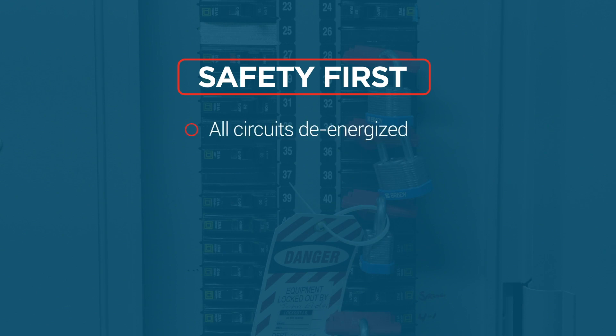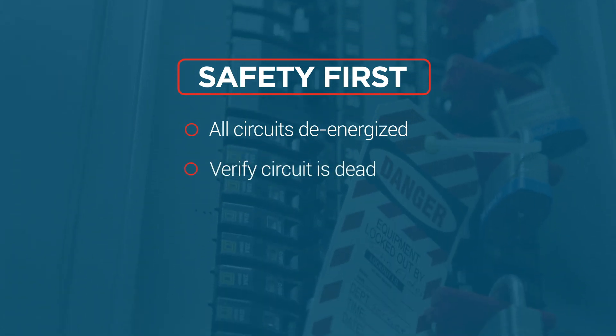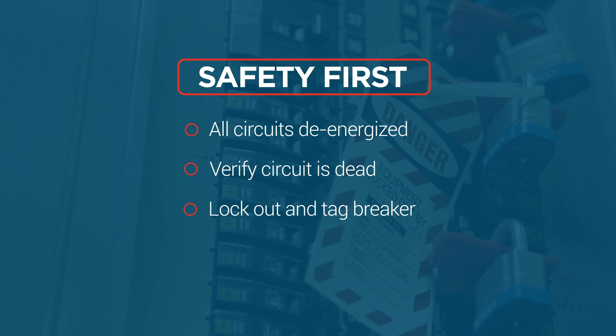All circuits should be de-energized prior to any wiring or service. Remember, many of our controls will have more than one circuit that will need to be turned off. After de-energizing the circuit, verify that the circuit is dead, then lock out and tag the breaker.